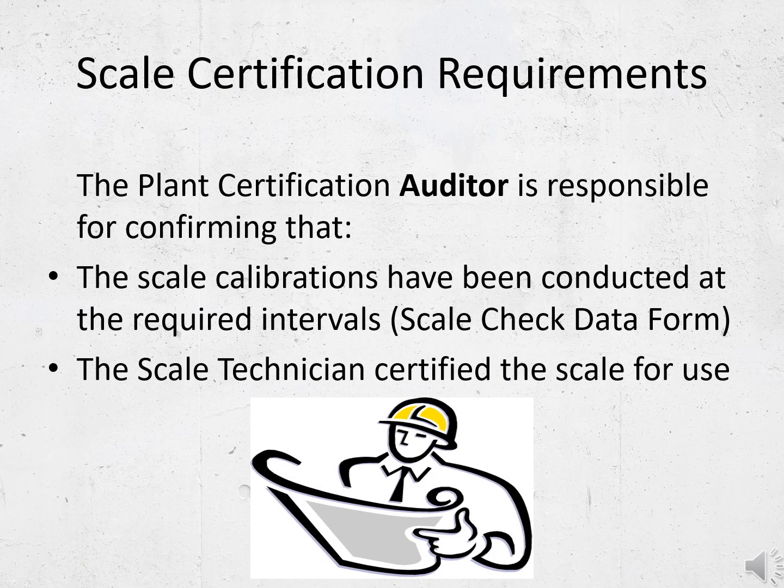Check that the scale calibrations have been done consistently and at the right intervals over the past 3 years, and confirm that technicians' reports contain all of the information required for this certification process.